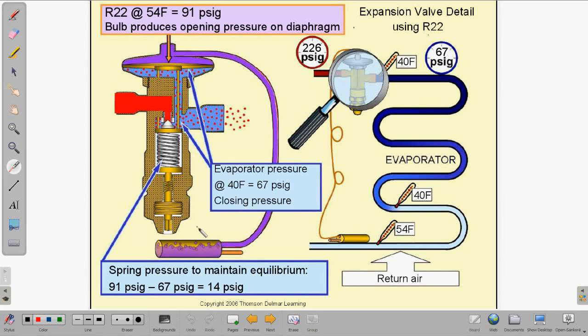Now, let's talk a little bit about what happens with all of these forces when things start to change. Let's say, for example, we take this sensing bulb off of the 54 degree outlet of the evaporator, and we drop it into a warm glass of water. What's going to happen is the warmth from that water is going to cause this refrigerant to boil even more. It's going to increase the pressure on the top of the diaphragm, push the diaphragm open, and allow more refrigerant to flow through to the evaporator coil.